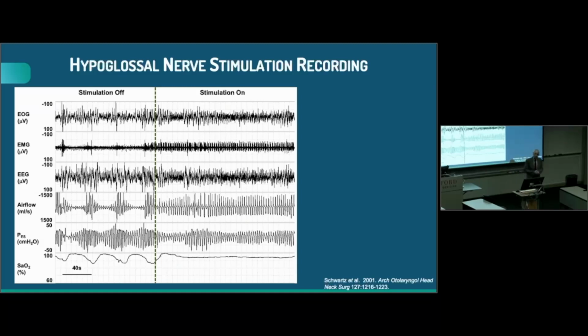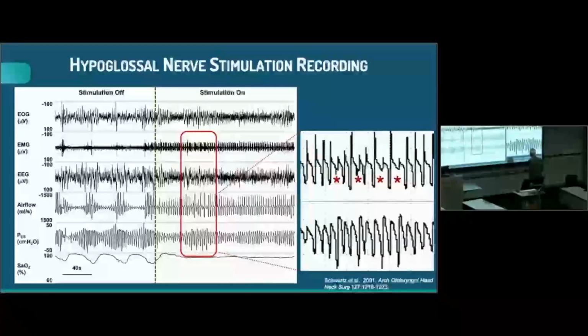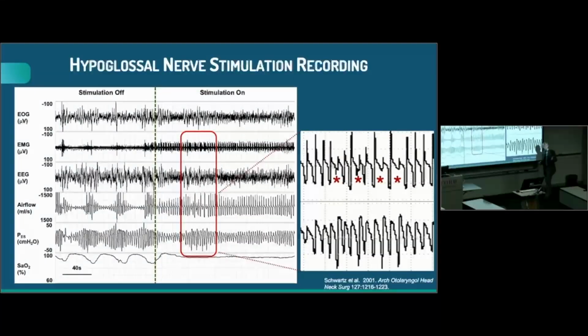And then as a result of the improvement in ventilation, what we see here is that the oxygenation improves and sleep continuity improves. But there was a glitch on this recording, because this stimulator, like the current Inspire device, is actually synced up with the respiratory cycle, but the syncing was not so good. I'm not sure how good it is now, but it wasn't so good. And it missed a breath or two, and surely enough, at the red asterisk, as the stimulator lost its way and failed to track the inspiratory phase of the cycle, what we saw was really clear. The airway shut down and went right back to its previously obstructed state, shown here in the obstructive hypopneas on the left-hand side.